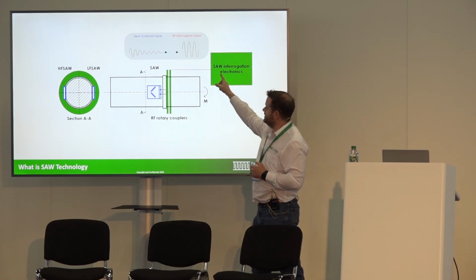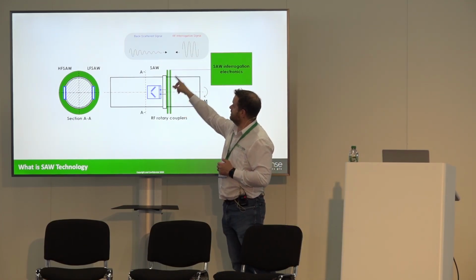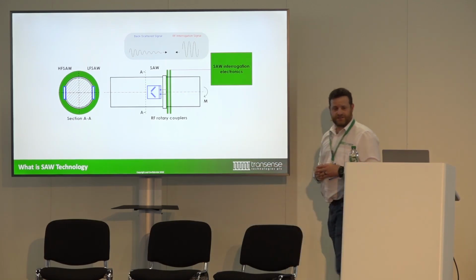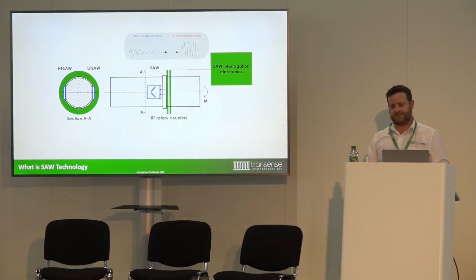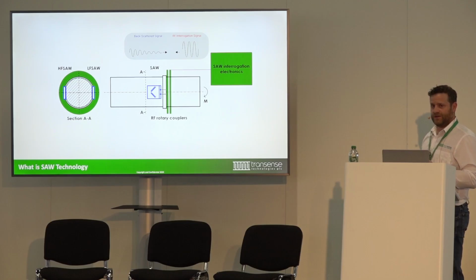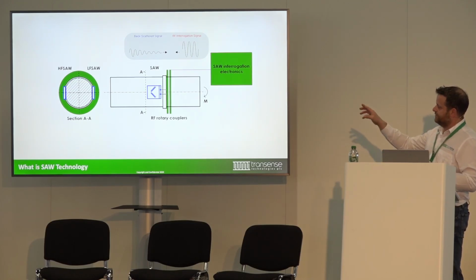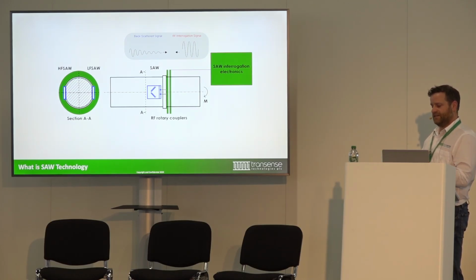We have our sensing element on the shaft, but electronics off the shaft. So we feed the SAW elements themselves with an RF signal. Our chiplets are designed to work at about 450 megahertz. The key thing is each one of the IDTs in the SAW system has a unique frequency. So we have a band around the 450, 420 to 450, and we divide that into 5 individual bands. We address each sensing element individually, and we listen for its response individually.